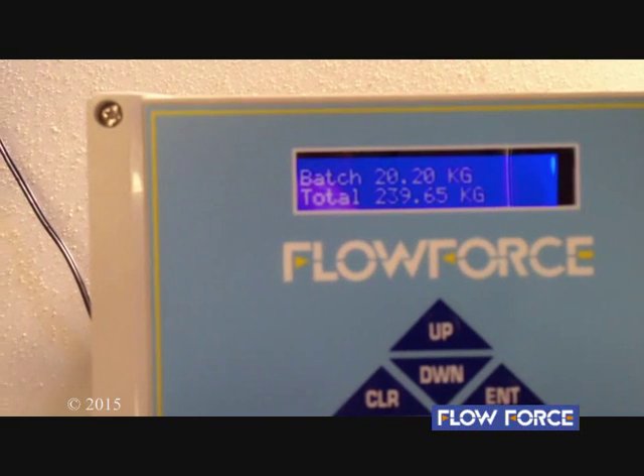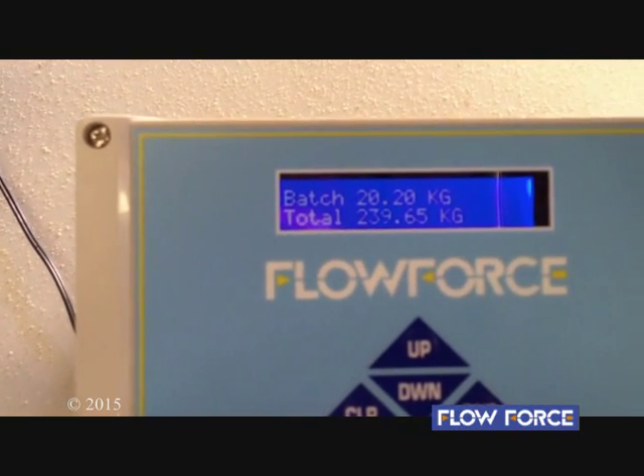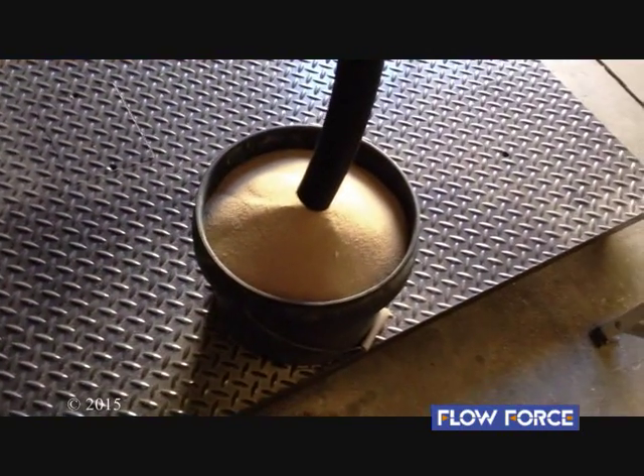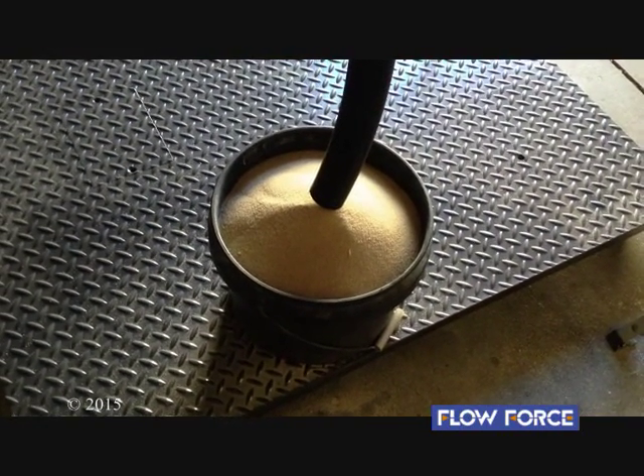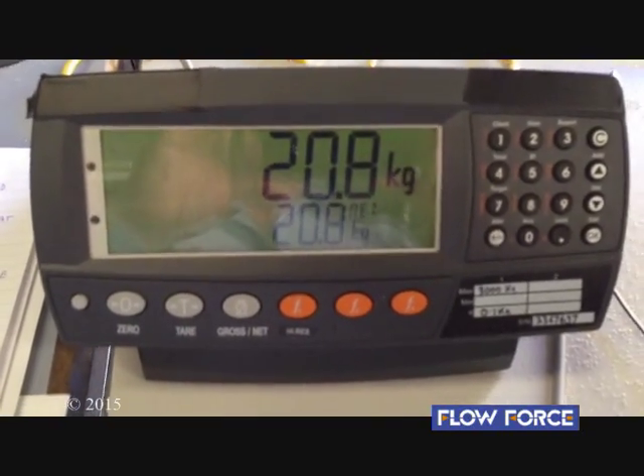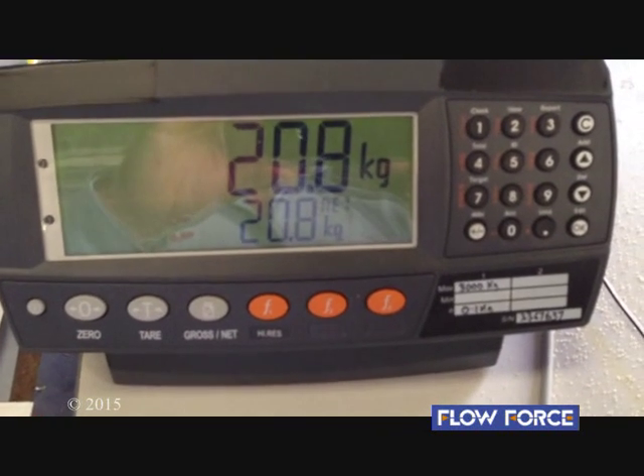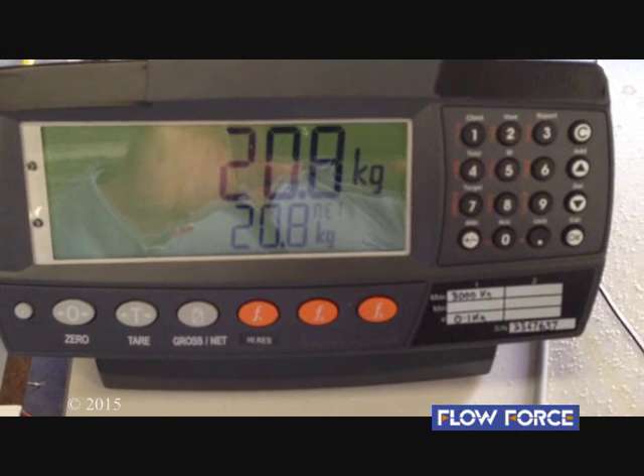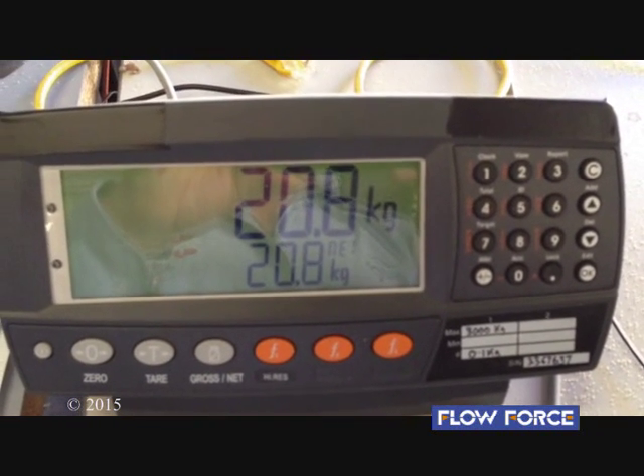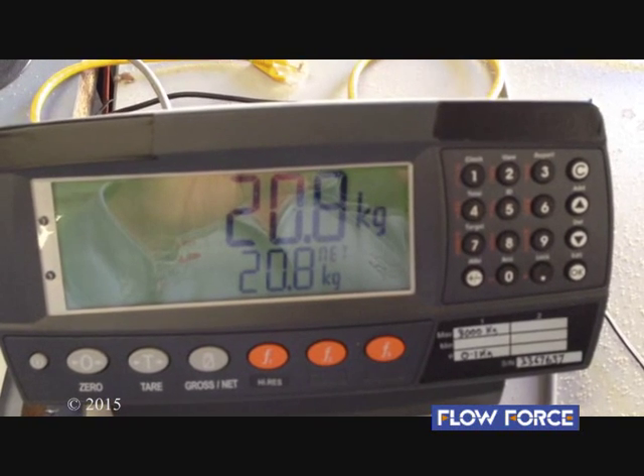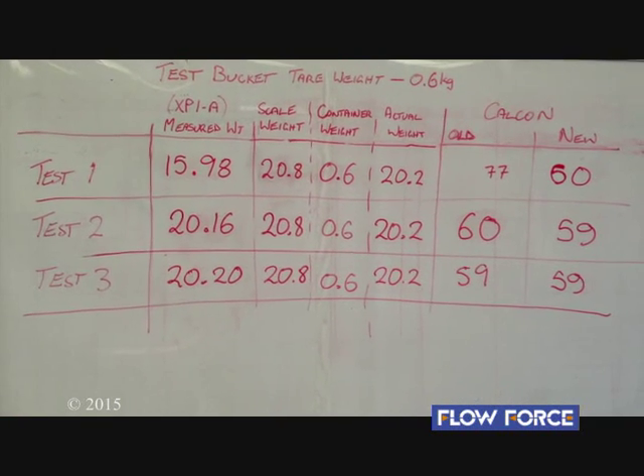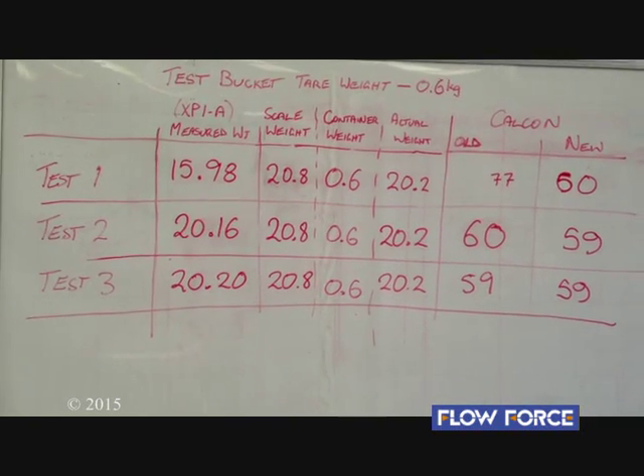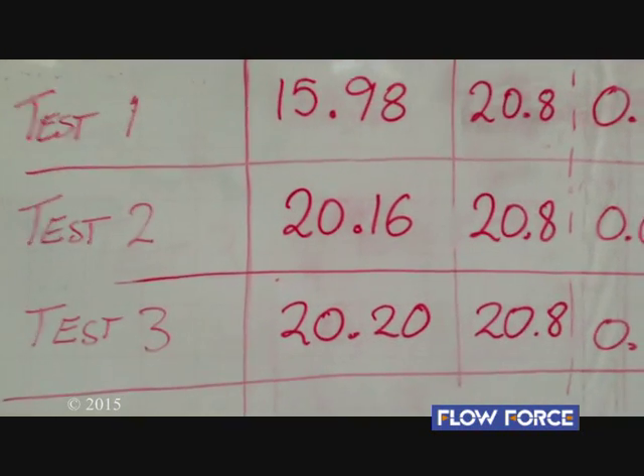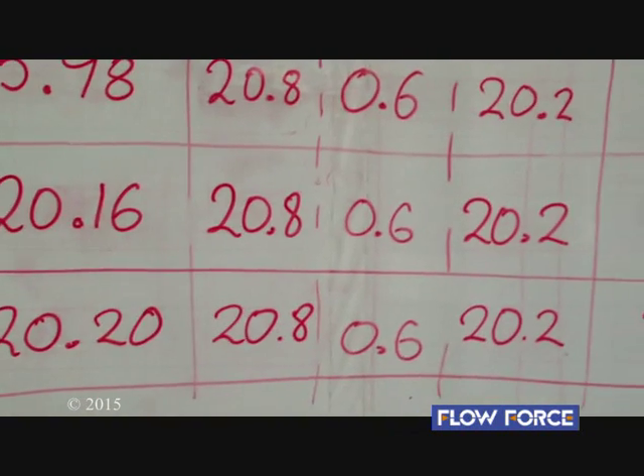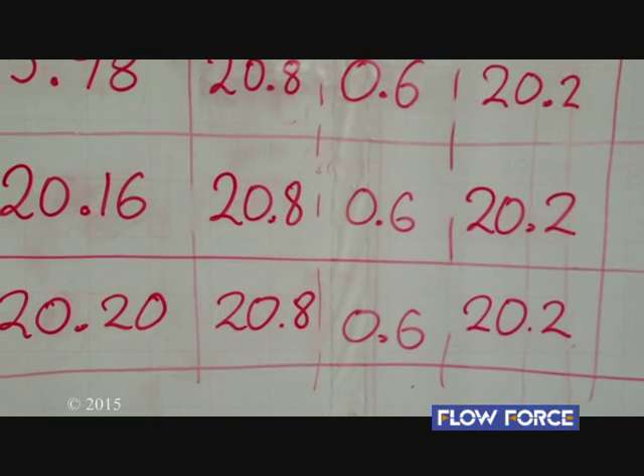So we'll do a check on the actual, measured weight. So our test container is on the scales, we have a scale reading of 20.8. We'll put this data onto our calibration sheet, get the new final weight, and put that data back into the controller for a final calibration. So we put the data onto our calibration sheet.